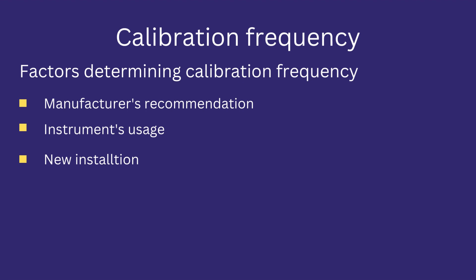New installation — whenever an instrument has been installed for the first time, it must be calibrated. This helps to detect any fault in the instrument, which can sometimes be difficult to detect because of its newly installed status. Sometimes a newly installed instrument requires minor adjustment, which is normal and becomes necessary. Operating environment is also a critical factor in determining calibration frequency. Because there are different environmental conditions at different locations — for example, at the technical floor, instruments can be subject to high temperatures, dust particles, and humidity compared to instruments installed on the production floor. Calibration frequency is therefore selected by considering the environmental conditions.